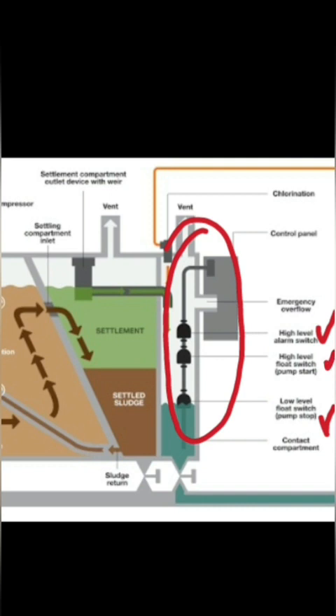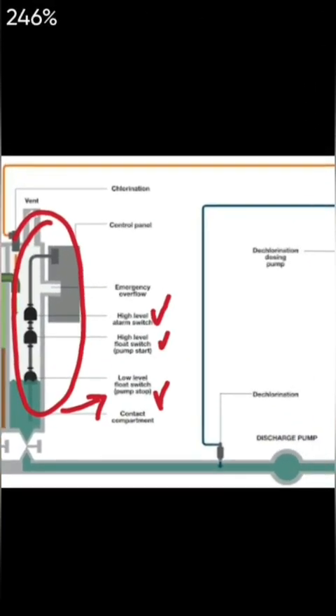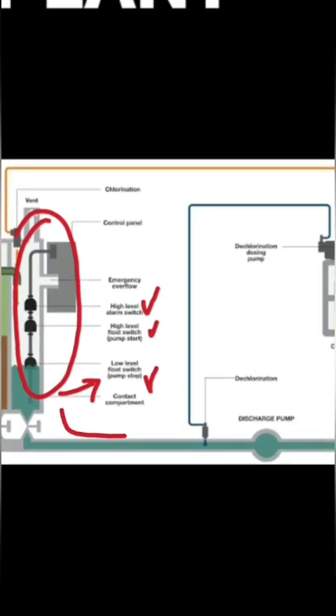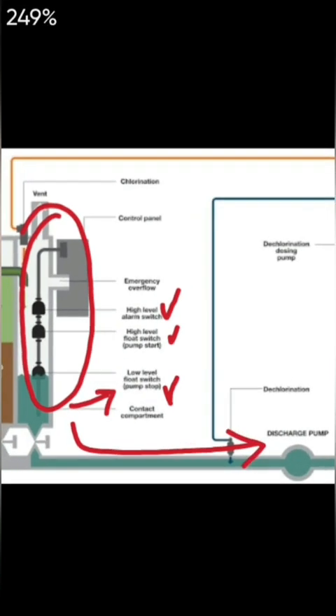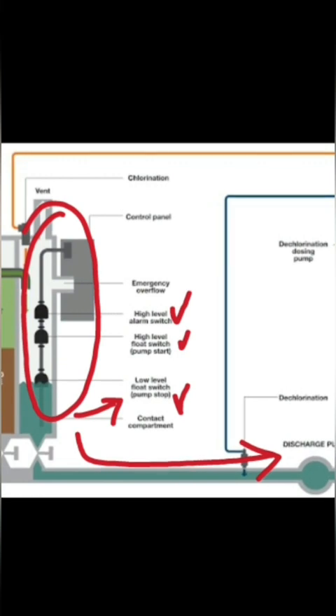The low level is for the stopping of the pump — the discharge pump. The discharge pump is here, as you can see. The discharge pump will start when the high level switch — the center one — gets activated. And when the low level gets activated, the pump will get stopped. If the topmost float is lifted, it will turn into the alarm, which is the high level alarm.